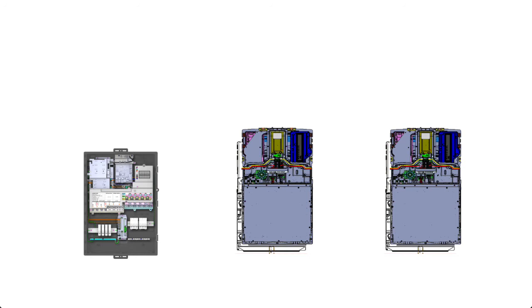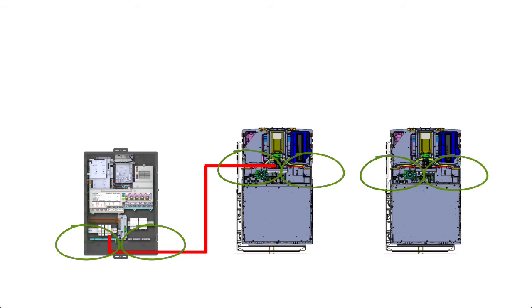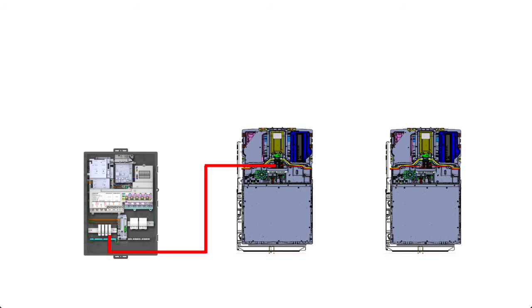Once each battery is in position, single phase battery circuit wiring is fed from the system controller across to the first battery. There are knockout options in the system controller and at each battery that will allow for surface mounting or for rear wiring access. After connecting into the first battery, a parallel connection can be made into a second battery. Additional battery circuits can be wired from the system controller as required.